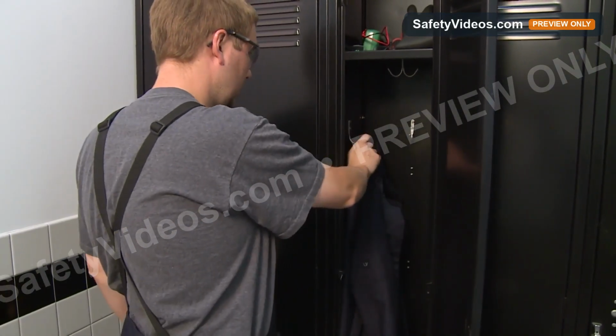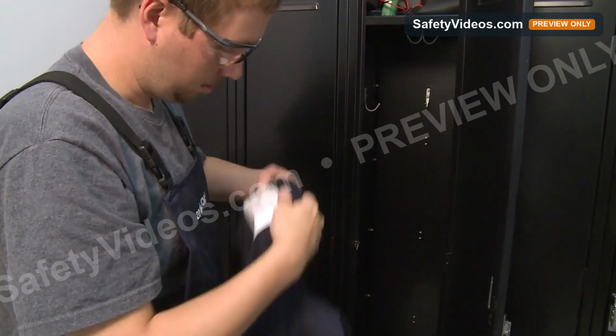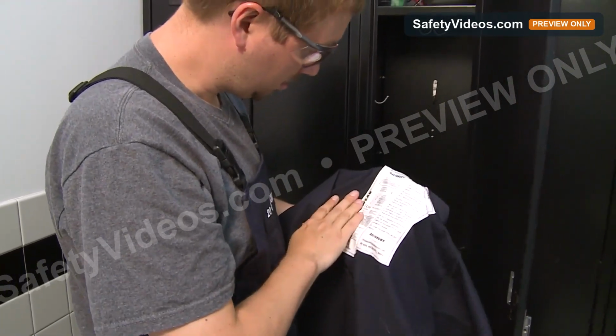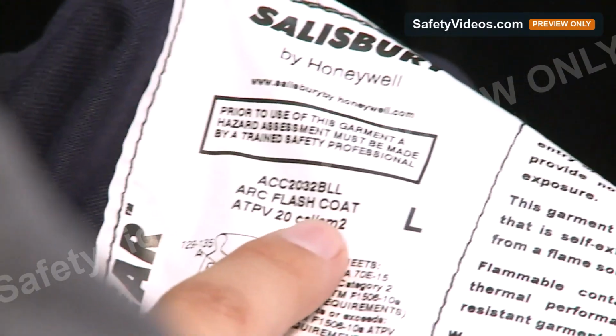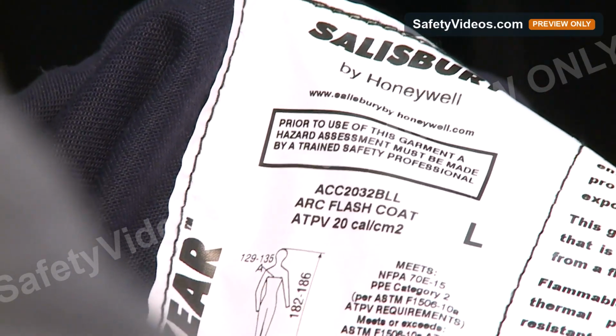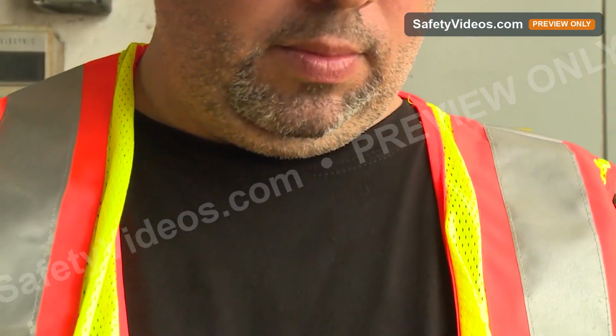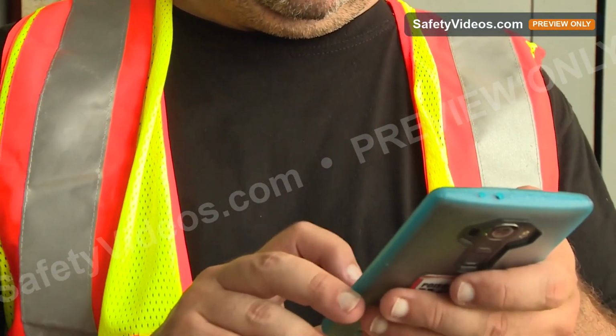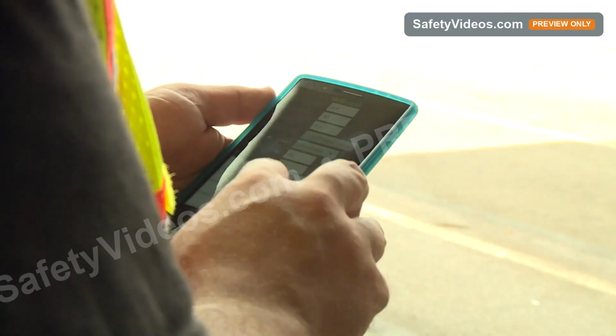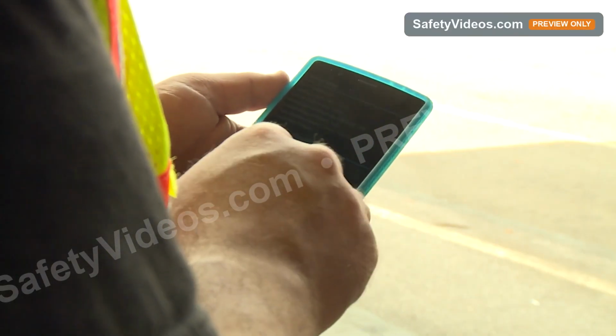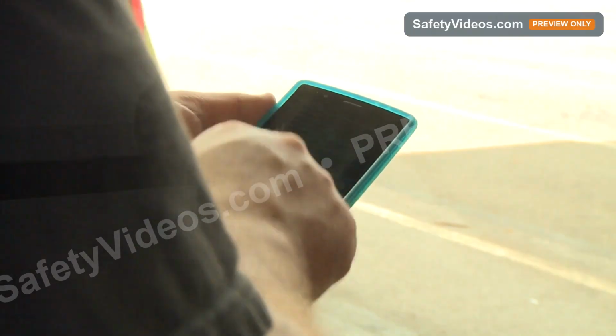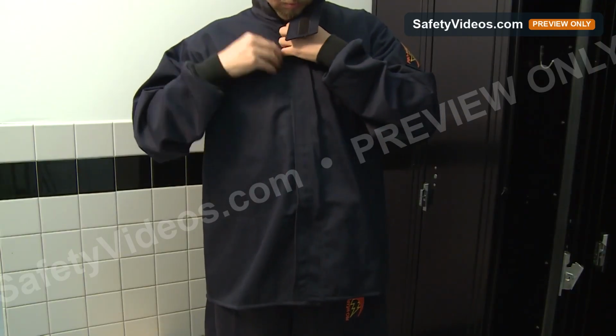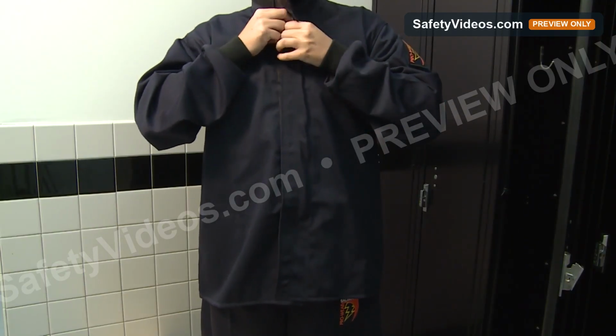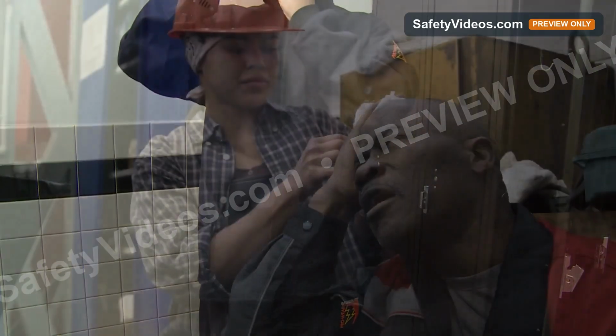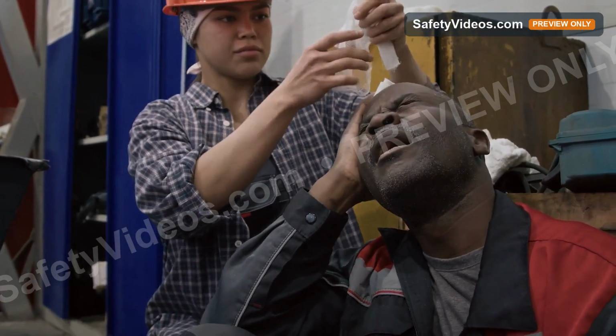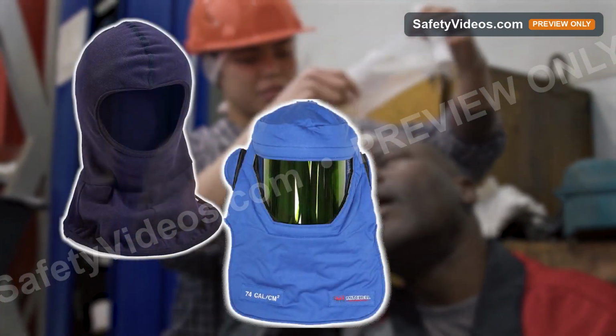This is why electrical workers always put on arc-rated protective clothing when they approach a potential arc flash source. Its arc rating describes how much heat the clothing can resist without damage. To calculate the arc rating you need for a particular task, you should determine how many units of heat you would receive if an arc flash occurred in the equipment you're working on. You can then choose clothing with an arc rating that meets or exceeds the protection level for that amount of heat.